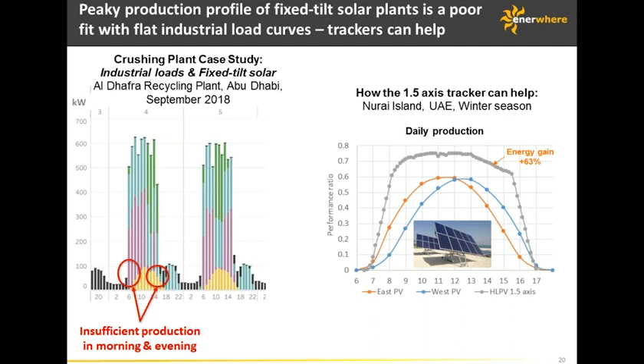Even if I ramp up the normal fixed tilt plant, I will continue to see a pattern where I just don't produce enough power in the mornings and evenings. The only way to fix that would be to oversize the PV plant dramatically, either giving up production at noon where I have to curtail, or dramatically increasing the battery size.